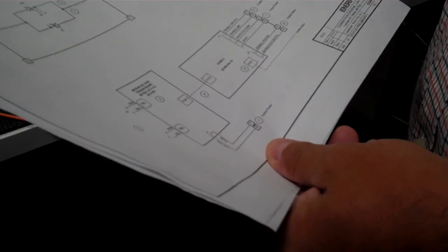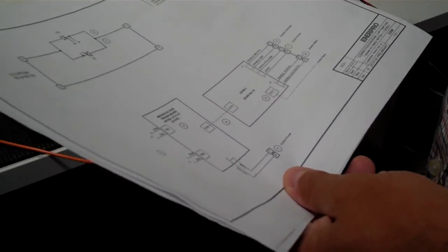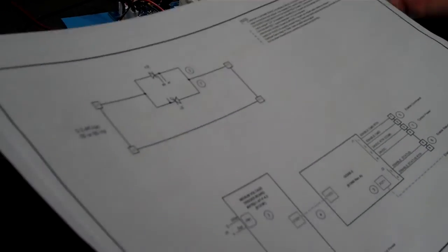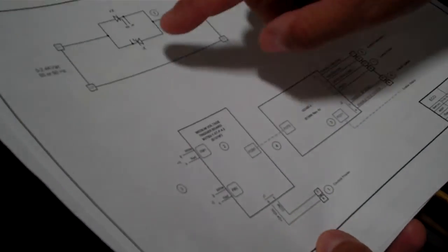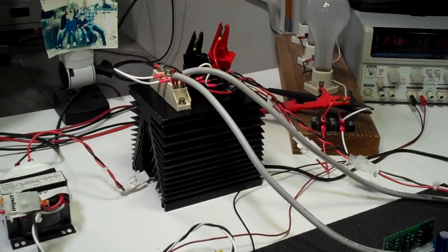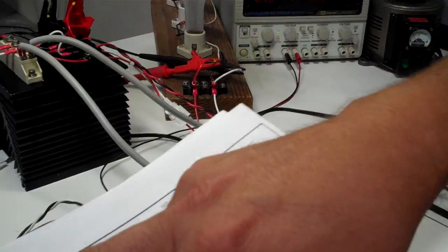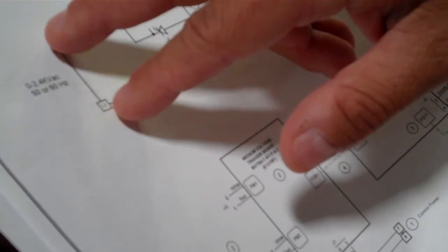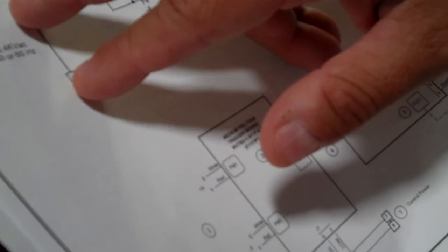That connection on JU1 will fire the two SCRs at the same time. Basically a 2-2 we've converted into a 2-1, and here we have the two SCRs in anti-parallel, and we have our AC input and our AC output. In this particular case we have 480, but it can be anywhere from 0 volts all the way up to 2.4 kV.